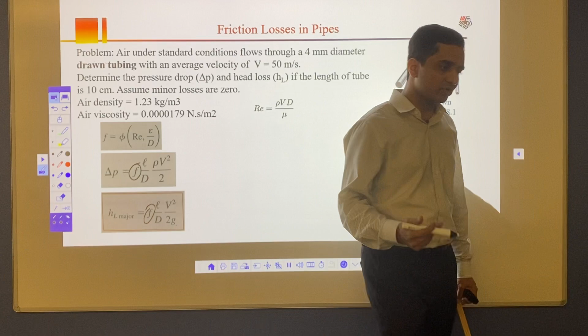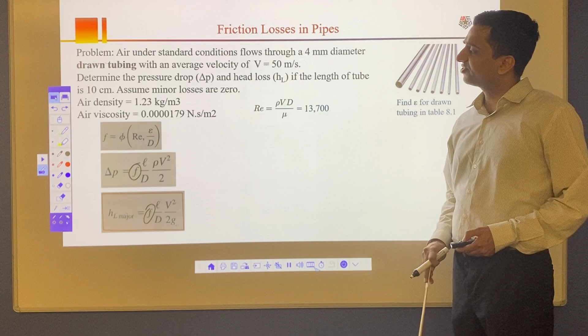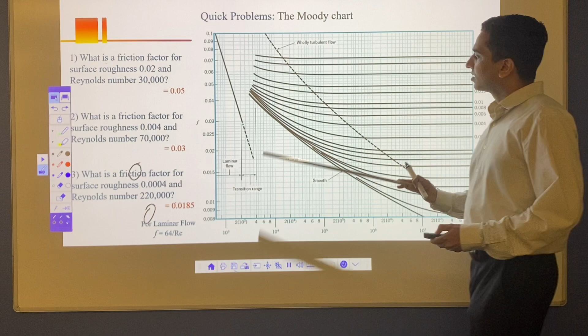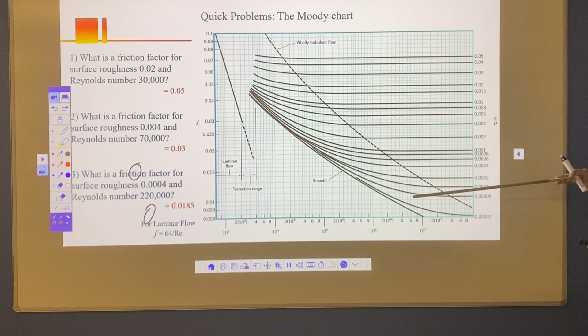Now in this problem, the very first thing you need to do for the friction factor is calculate the Reynolds number. For Reynolds number, you have velocity, density, viscosity, diameter. You can put the numbers in and calculate the Reynolds number, which will come to around 13,700. Now you use that 13,700 on the chart. You also have to calculate epsilon by d. The epsilon value for this drawn tubing is given in Table 8.1, and the diameter is given in millimeters. Calculate that epsilon by d, then mark a horizontal and get your friction factor, and once you do that, you should be able to calculate delta P.